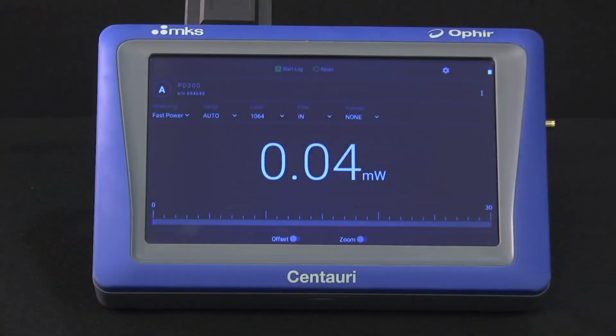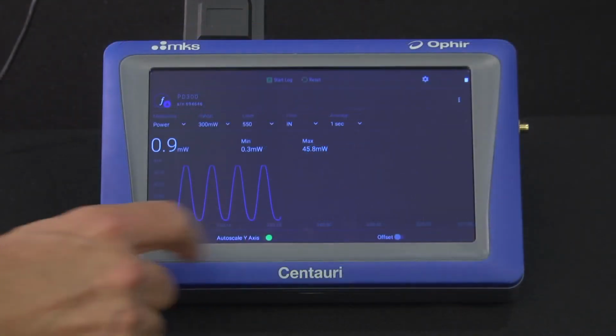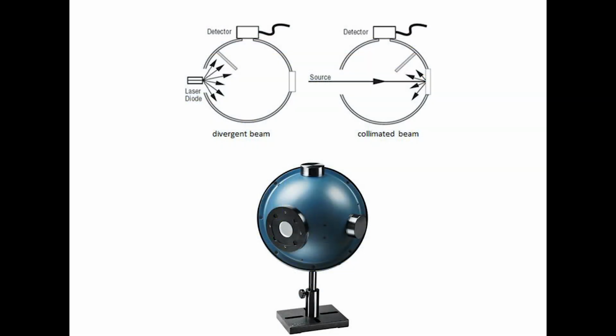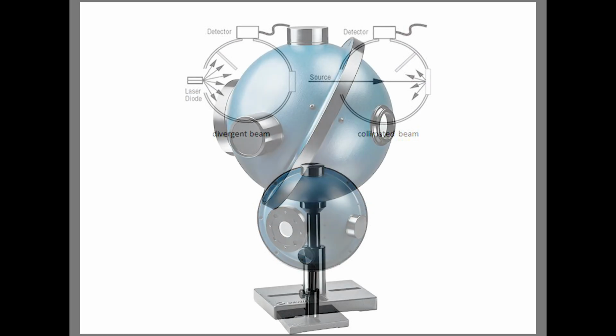Parallel laser beams can also be measured, taking advantage of the fact that the integrating sphere effectively attenuates the beam by having only a small fraction of it reach the sensor. For example, we can make use of the fast response of a photodiode sensor and measure powers that, if directly incident on the photodiode, would saturate it. Also, the sphere is essentially insensitive to misalignment of the beam.